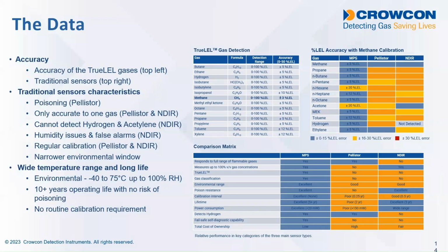So there are lots of benefits of the MPS sensor over both the Pellistor and the infrared gas detector. The first being the true LEL accuracy. I've said before that a Pellistor will detect lots of different gases and vapors, but it will only be accurate for the gas that it's calibrated with. If it is calibrated with methane, it will detect hydrogen, but it will give you a slightly incorrect reading. An infrared sensor will also detect other gases and vapors.